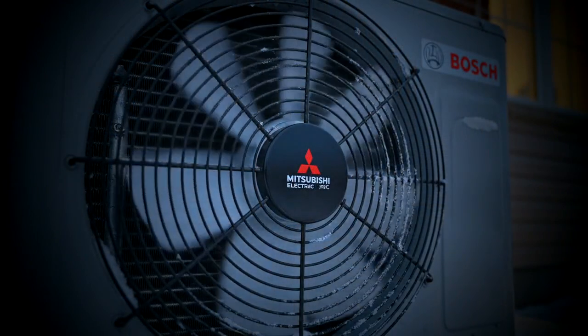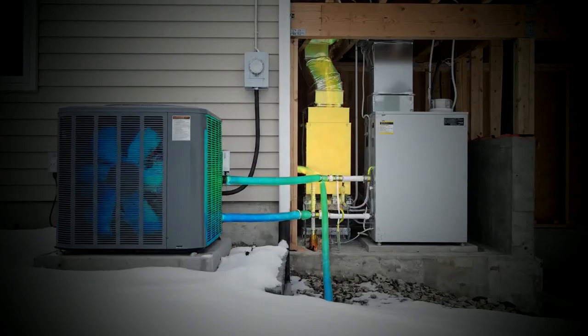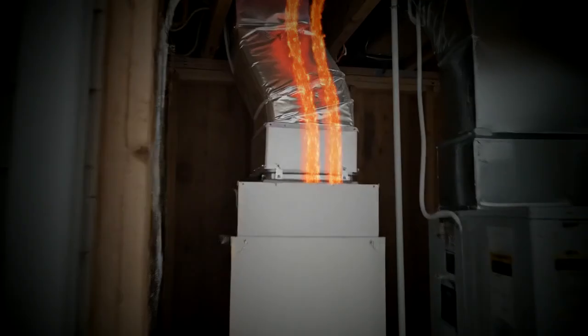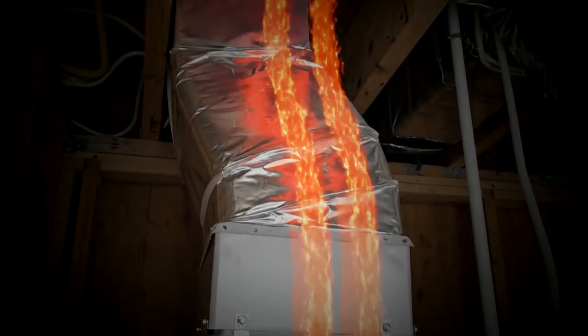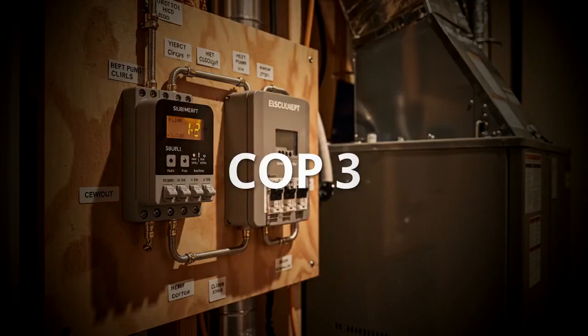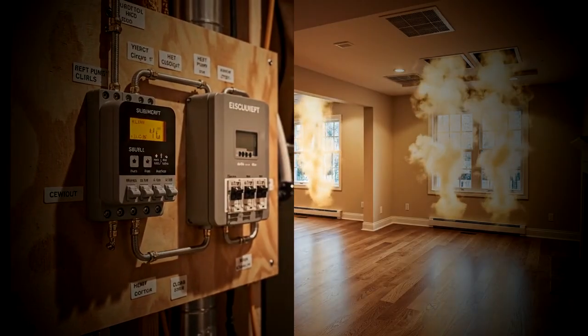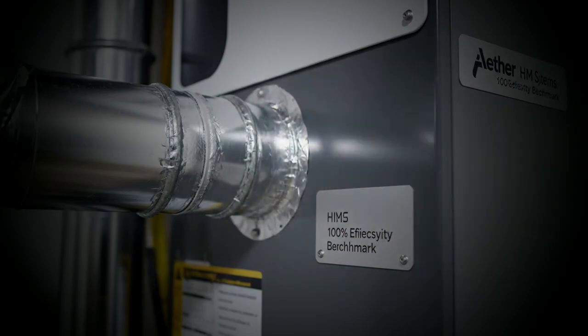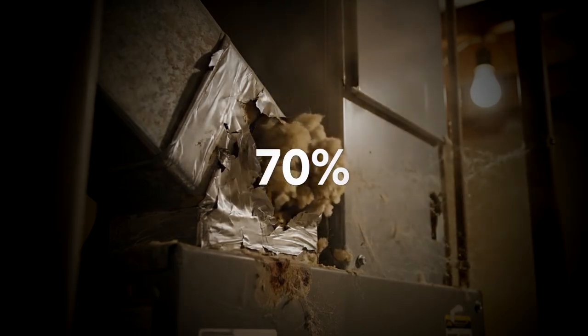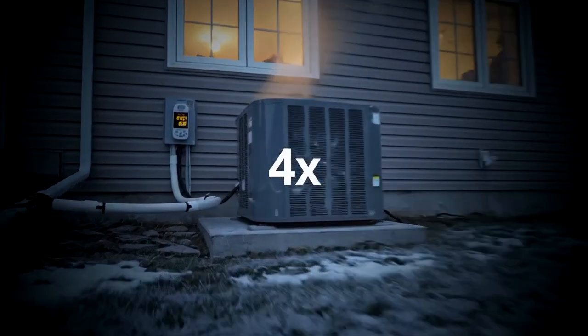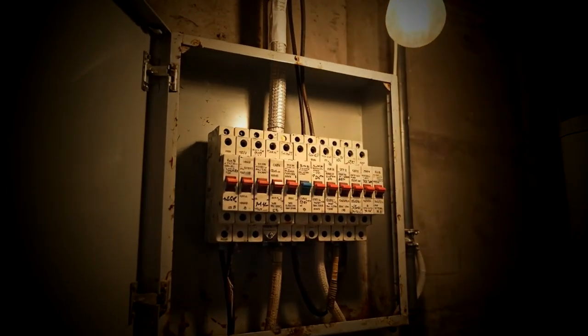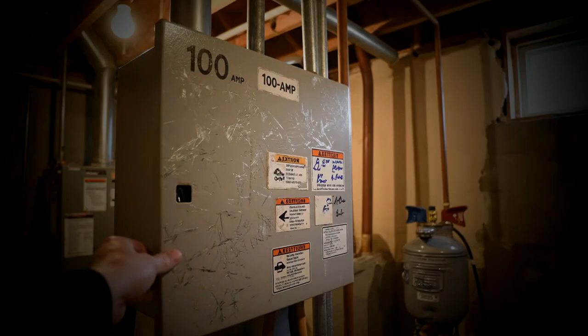A modern cold climate air source heat pump, units from Mitsubishi, Daikin, and Bosch, operates at between 250 and 400% efficiency. Not a misprint. The unit moves heat instead of generating it. For every 1 unit of electricity consumed, it delivers 2.5 to 4 units of heat into the home. That ratio is called the coefficient of performance, COP. At a COP of 3, you are getting 3 times the thermal output per dollar spent on energy compared to a gas system running at 100% efficiency. Against a gas system running at real-world 70% efficiency, you're getting roughly 4 times the output per dollar. That is where the bill cuts in half. That is the math, not marketing.